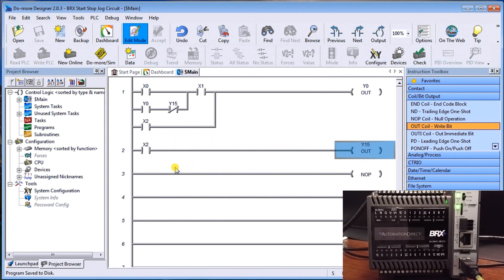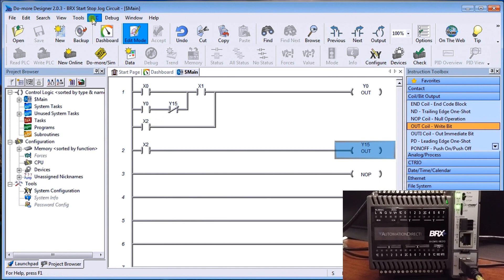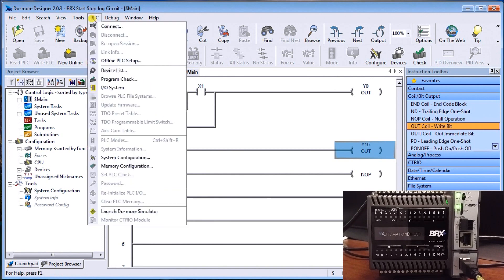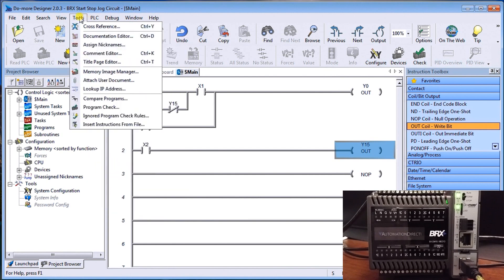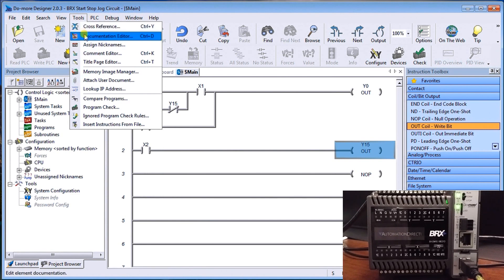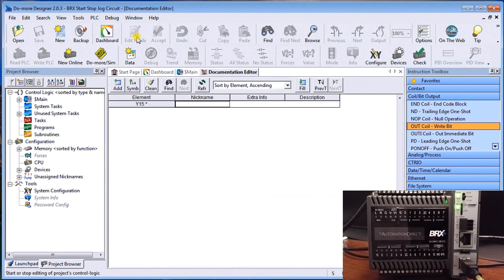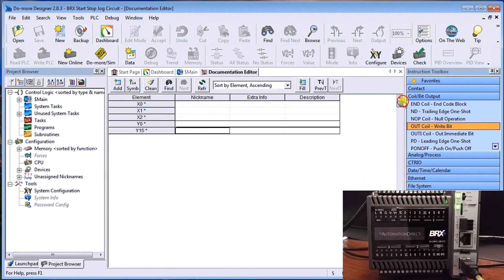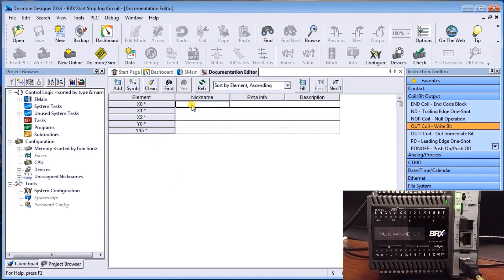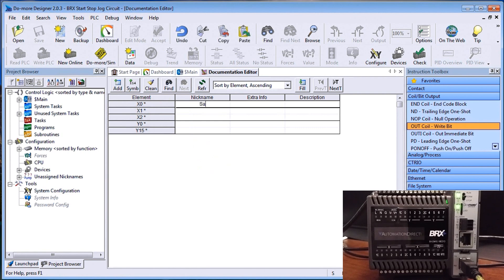You'll notice that it's very hard to read because I don't have any documentation. So what we should do is actually do some documentation on this project before we go too much further. And in order to do so, if we go to the document editor, which is under tools, or you can hit control D, the document editor comes up. And what you'll notice is that without doing anything, it already knows that all of those rungs that I've accepted and changed, it says you don't have anything for it. That's what the asterisk means. You don't have any comments. So let's put some nicknames in for each one of these.